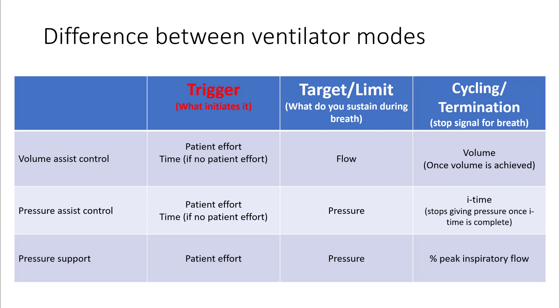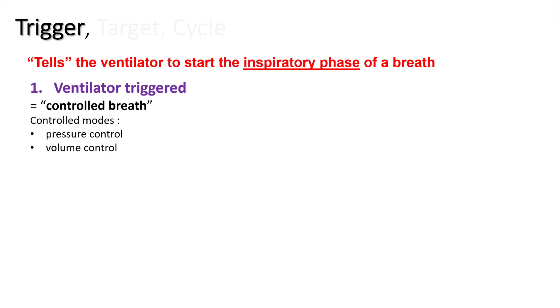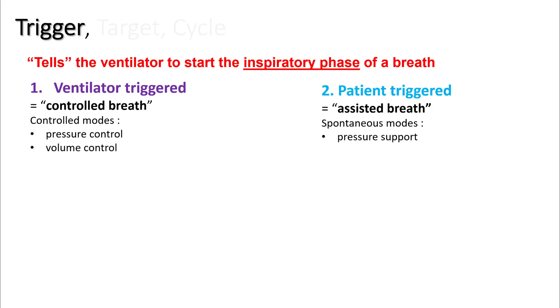For example, in volume assist control, the trigger is either patient effort or time, the target is flow, and the cycling occurs when the volume is achieved. Trigger tells the ventilator to start the inspiratory phase of the breath. There are two types of triggers: first is the ventilator trigger, also called controlled breaths, and second is the patient trigger, which is called assisted breath.